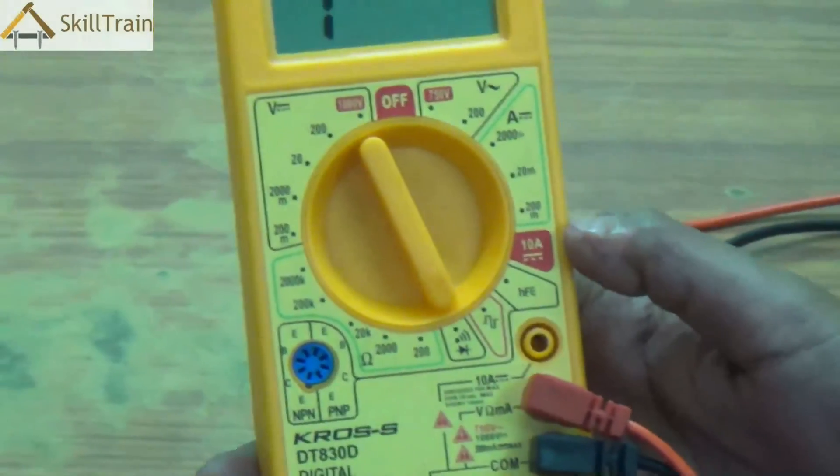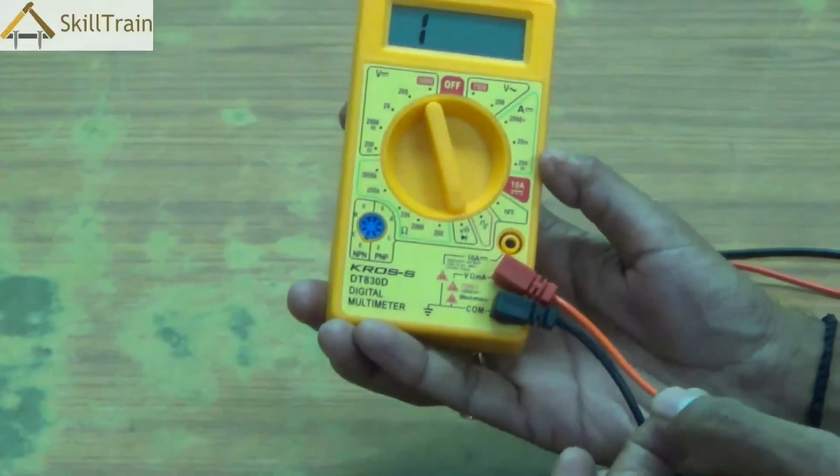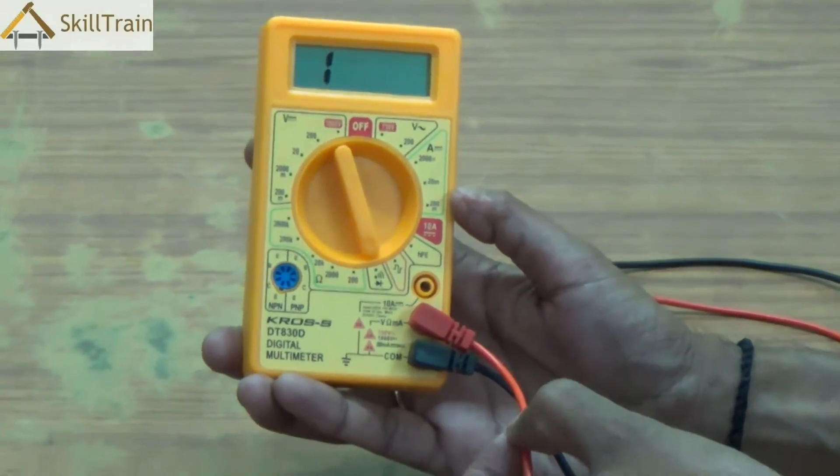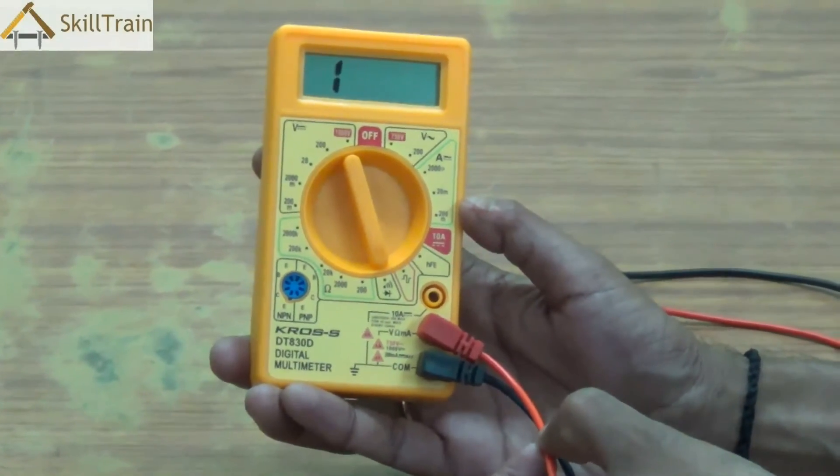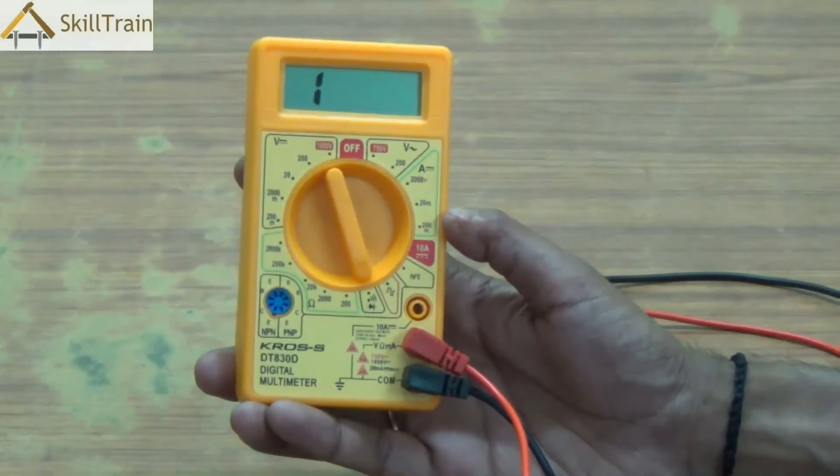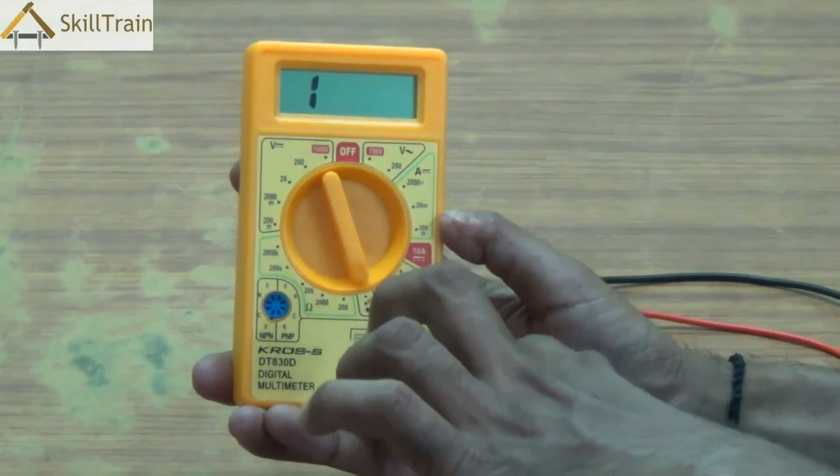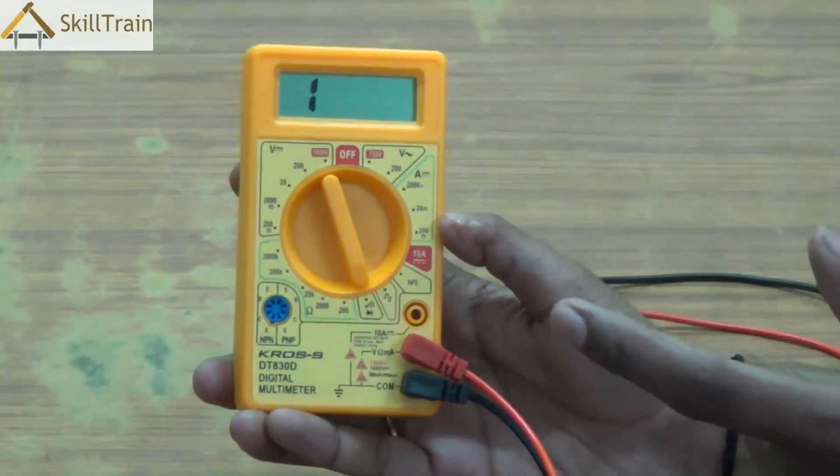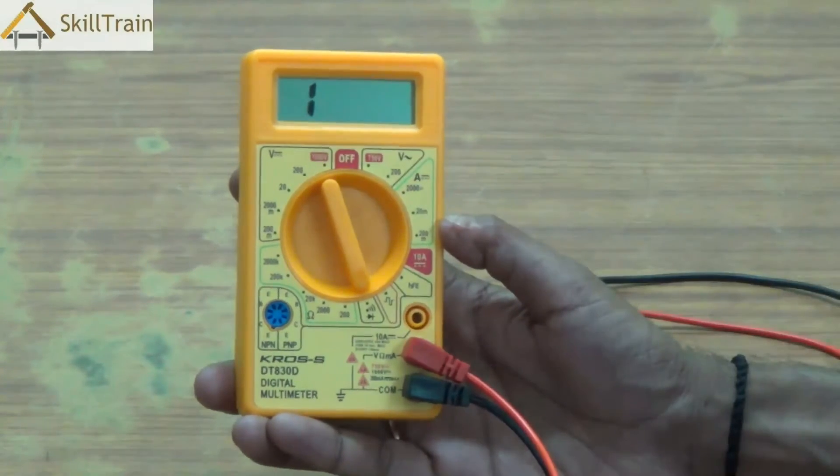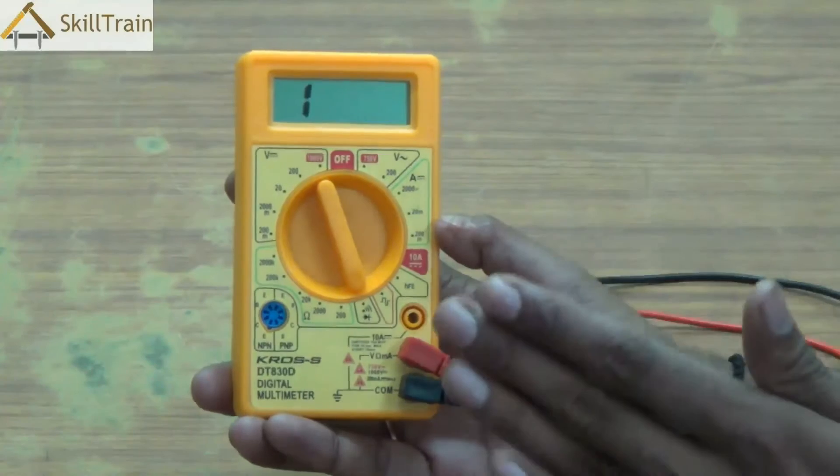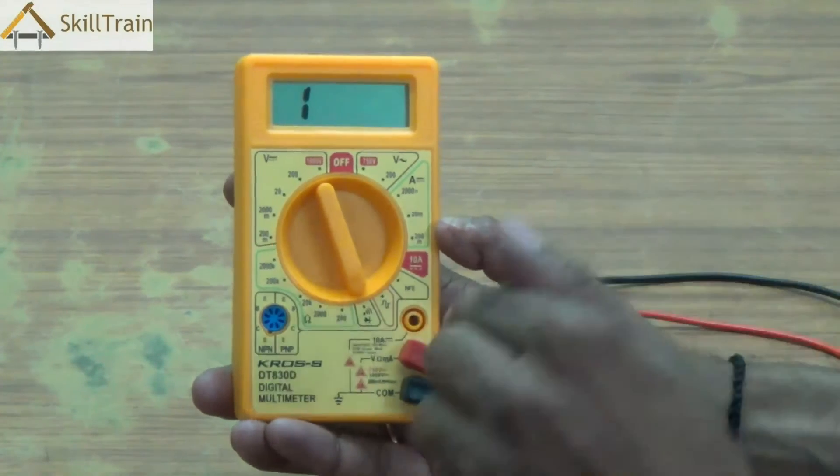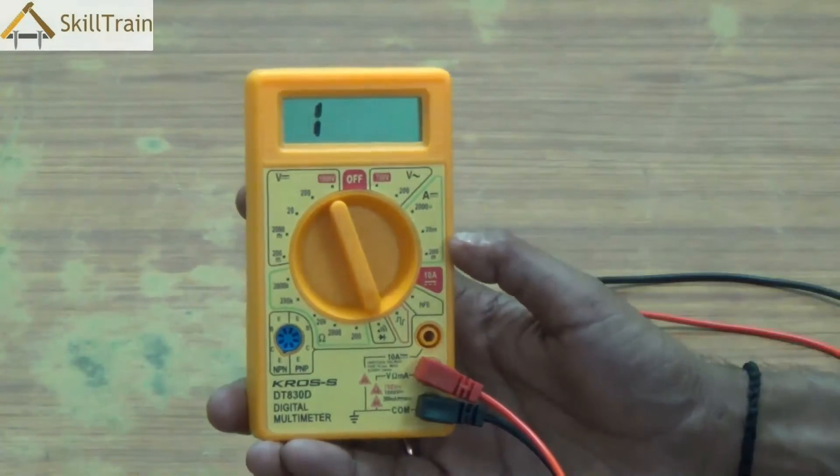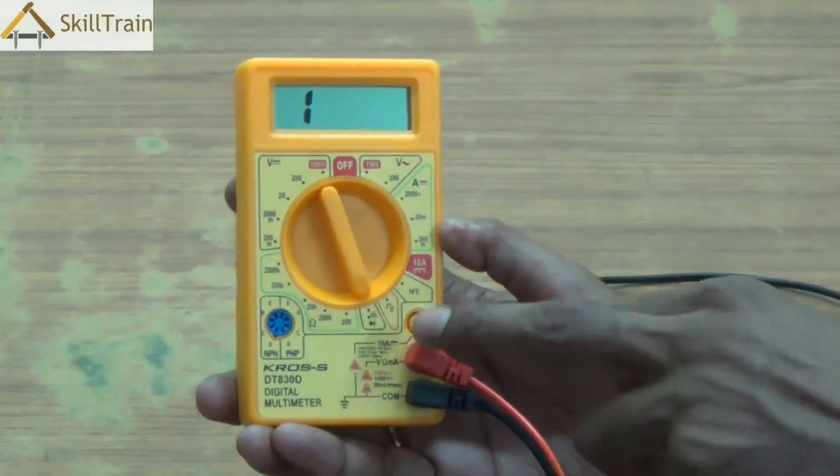The reason why we do this beep testing is, for example, when we are checking a wire and we want to check whether the wire is broken in between. Typically, broken wires are called open wires. So if you want to check whether the wire is broken from inside, you will not be able to find it out looking at it from the outside. So in order to check the continuity, we use the beep or continuity testing, which means you touch the two ends of the wire using the black and red probe, and if you hear a beep sound, it means that the circuit is not open and the wire is proper. But if you don't hear a beep, it means that the circuit is broken somewhere and you need to fix it.